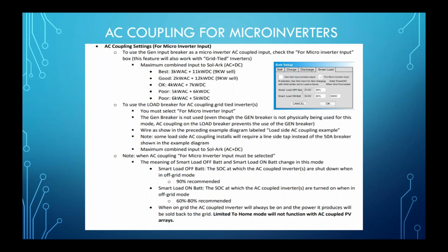The other way to connect, if you're going to AC couple inverters, is to use the load breaker. So when you're wiring this up in the Sol-Ark, you can use the generator input breaker and land it there, or you can use the load breaker and land it there. Either way, you want to check this for microinverter input, which now says AC coupled input on the smart load. And if you use the load breaker, even though the generator breaker is not being used, connecting AC coupling onto the load breaker will prevent the use of the generator breaker.